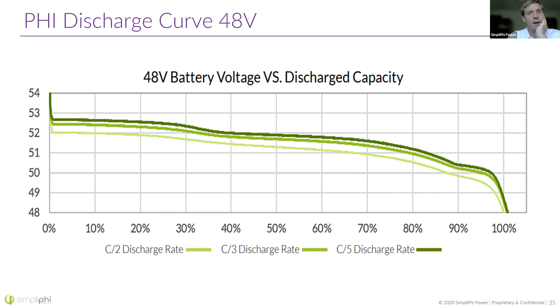If you set that around 51.2 to 52.8 volts, you're keeping your battery more charged. Looking at this curve - I should clarify, this shows percent the battery is discharged - at 51.2 to 52.8 volts, if you're drawing quickly you might be 65% discharged, meaning 35% of the energy is left. But if you're drawing at a slower rate at that same voltage, you could be 85% discharged. So keep in mind, it depends on how quickly you're discharging the battery.